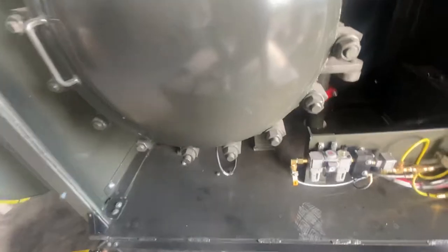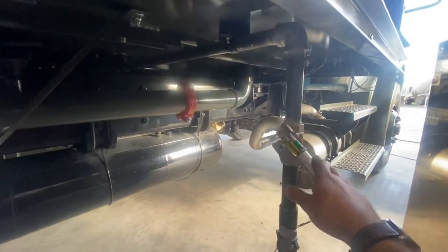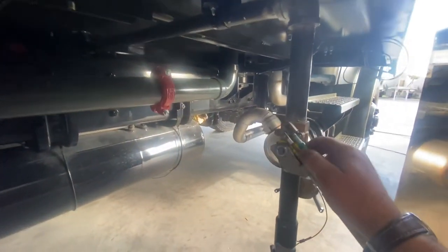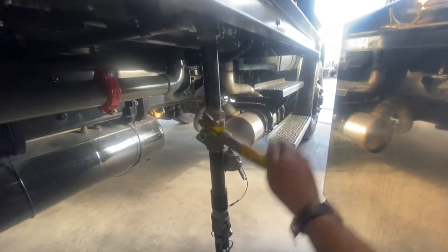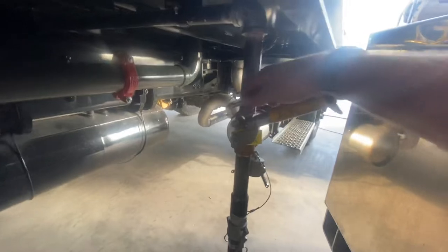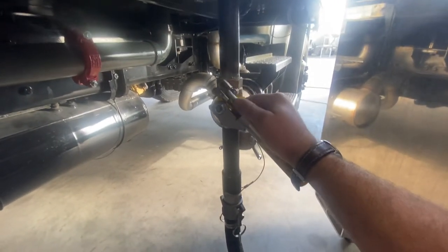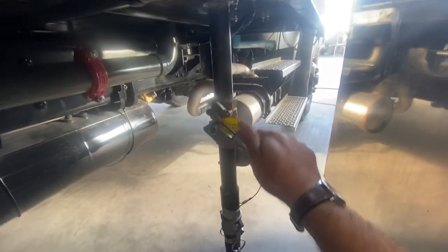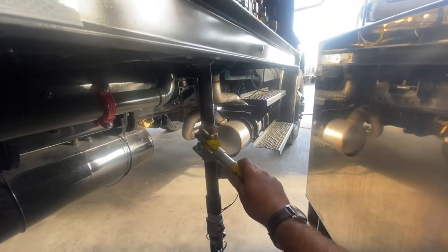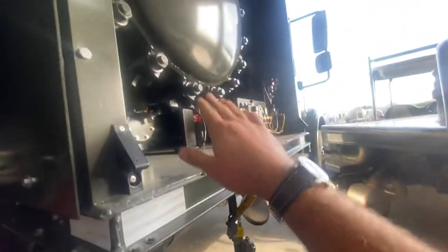the fuel down this line and then down to this spring-retracted — it's called a dead man ball valve. If you don't have anything blocking this area it'll go back. What we do is set a bolt right there to leave it open, because you're going to get around 200 gallons of fuel out of the filter separator.